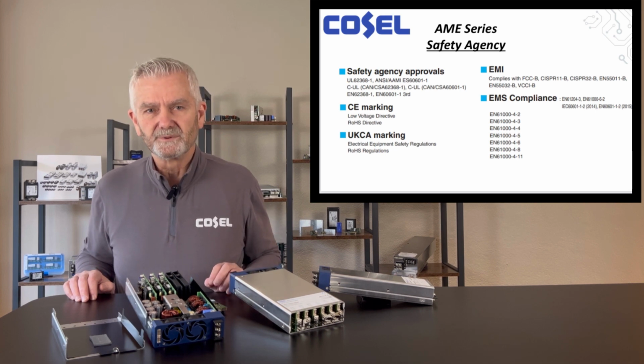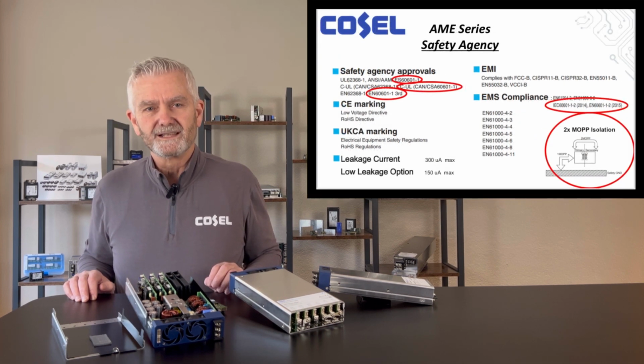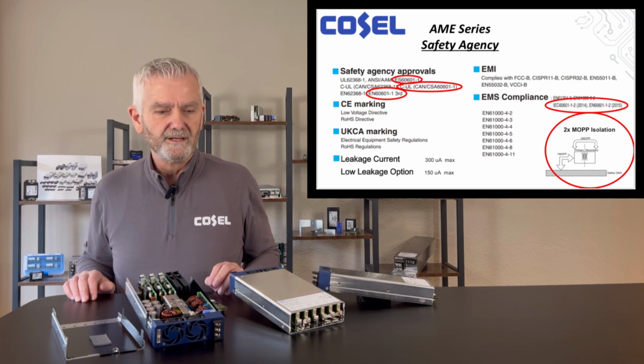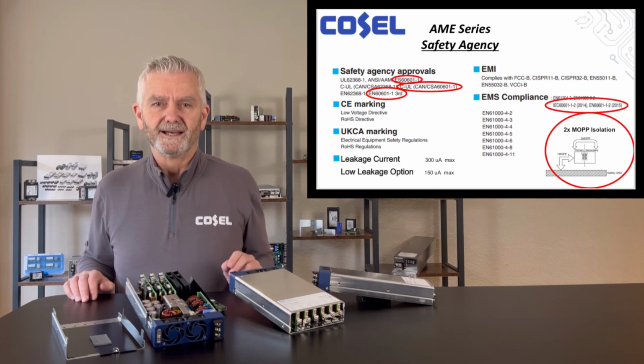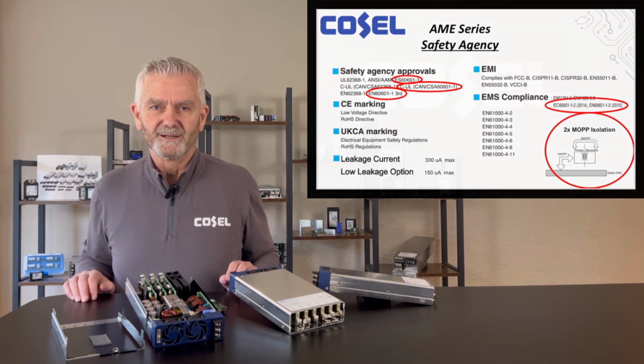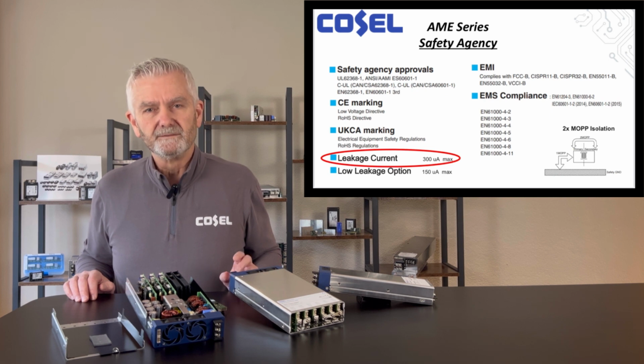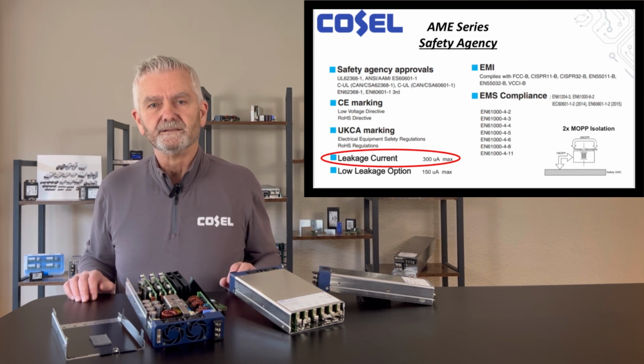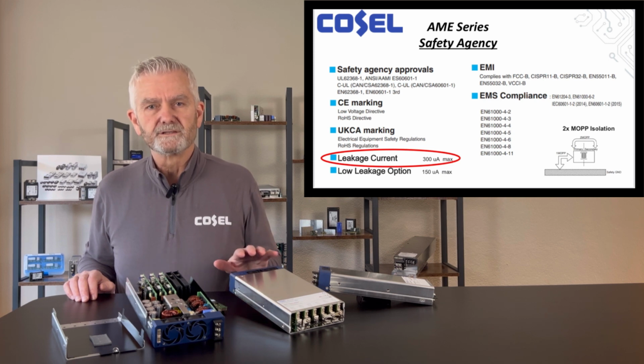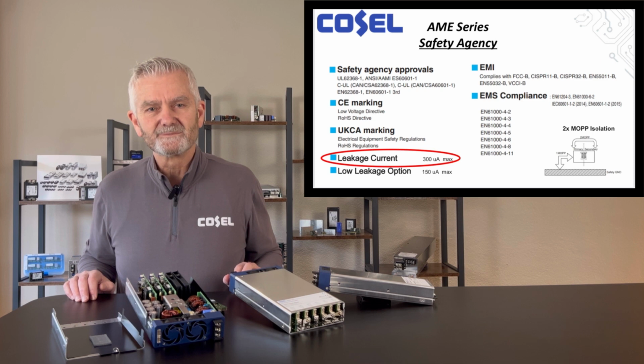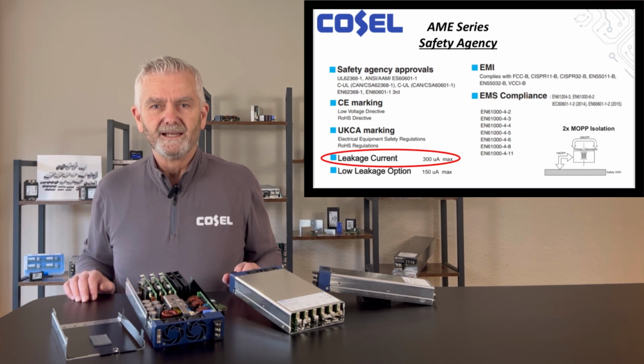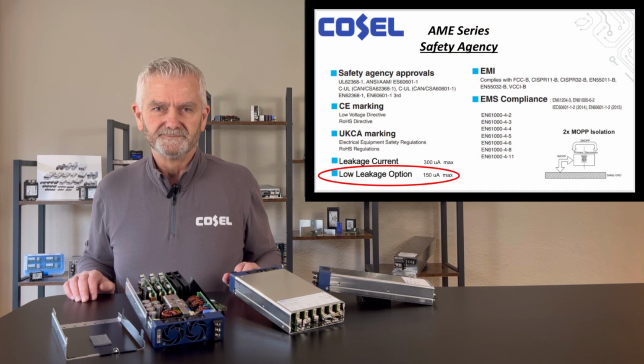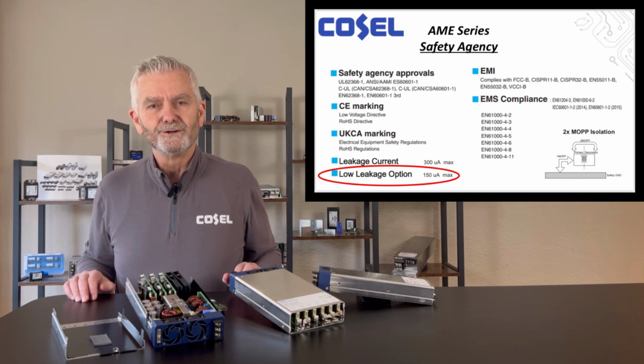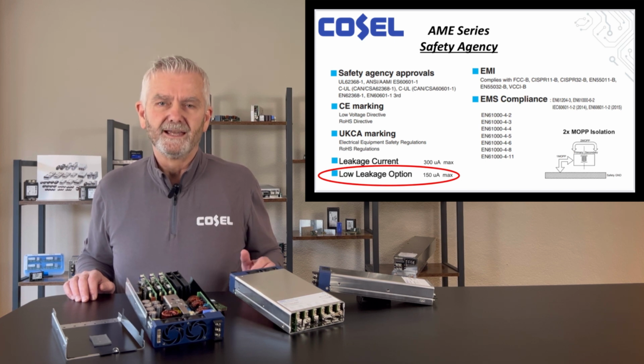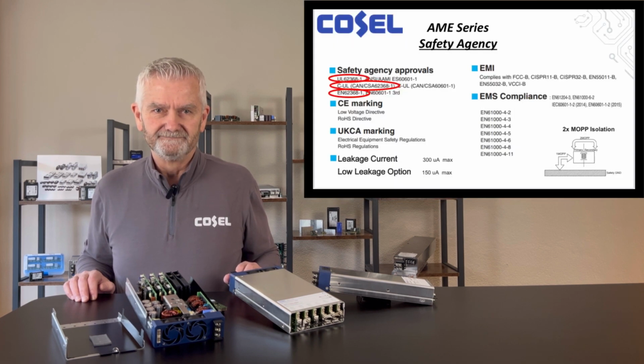The AME series boasts compliance with stringent medical safety standards such as UL 60601-1 with 2x MOPP primary to secondary isolation, ensuring peace of mind for critical applications. Leakage current on multiple single output supplies in a system are additive. However, for all possible combinations of outputs, the AME series has a maximum standard leakage current of 300 microamps at 240 volts input and 100% load. The low leakage current option further reduces the maximum specified leakage current to no greater than 150 microamps at 240 volts input and 100% load.